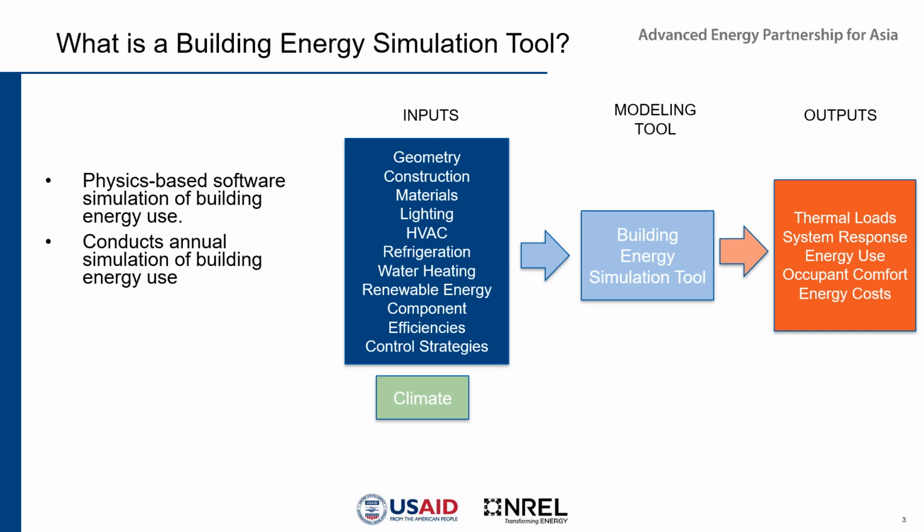Usually hourly data is available, so we know, for example, the temperatures outside, the solar radiation, the wind, the humidity and so on, a series of situations that we can take into account together with those inputs. The tool itself is, as I mentioned, a physics-based tool that usually, not always, uses hourly data to run, let's say, annual simulations. Usually the climate files involve a full year. There are different climate files to use. And then from all of that, it generates thermal loads, the system response, how much energy is used every hour, occupant comfort, and then obviously, because we know the energy at each time, we can calculate the energy cost.